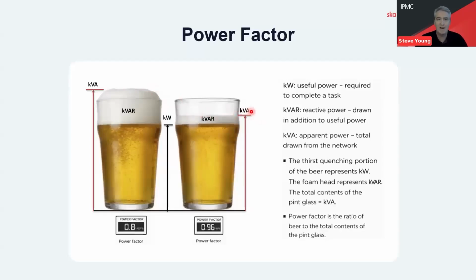The pint on the right-hand side is with a corrected power factor, and that is through mitigation. That's through using a power factor correction unit to supply reactive power, or VARs if you like, so that we don't have to draw it from the grid. Consequently, that can have a payback. But we must be very careful in the selection of that equipment to make sure that we don't get a technical conflict. The old pint pot analogy. We like the pint pot analogy.